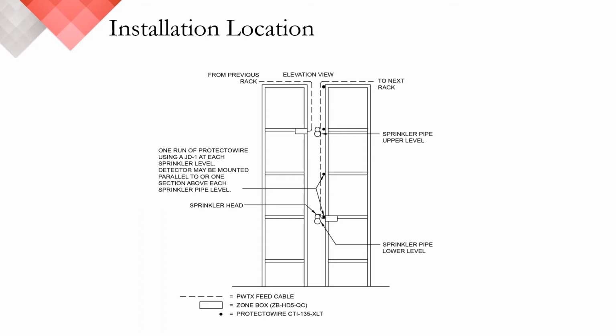Now, in theory, this sounds fairly straightforward, but there are always on-site challenges with finding the balance between offering the required proximity detection of being in the rack and finding a safe space to install the detector. Some of the newer automated racks do not have a flue space, or that space is significantly reduced. In this case, we recommend using some installation creativity, as many of the new racking systems available today will have a reverse channel that you can often locate the detector in, and it protects the detector perfectly.